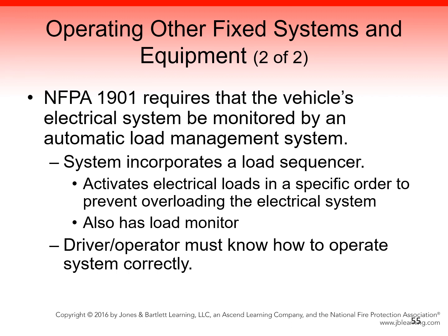A system that is protected with an automatic load management system incorporates a load sequencer, which is a component that will activate electrical loads in a specific order to prevent overloading the electrical system. The electrical system also has a load monitor, a component designed to prevent any additional electrical loads from exceeding the fire system's capabilities. In these circumstances, the system will perform load shedding, in which a component deactivates unnecessary electrical loads in order of necessity and to prevent damage to the system.